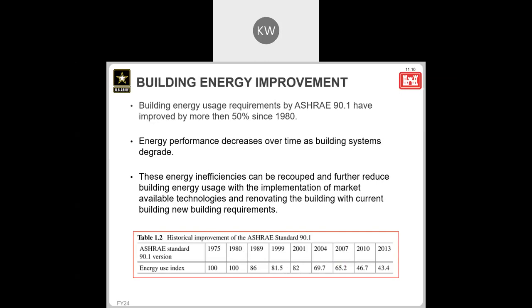However, our facilities' performance degrades over time, due to the effects of the environment on the building envelope, the HVAC losing efficiency as equipment ages, leaks, and things to that effect. We can lose in the neighborhood of 10% in energy performance over the life of the building. So these are things to be cognizant of as we look toward retrofits and energy improvements in the renovation process.